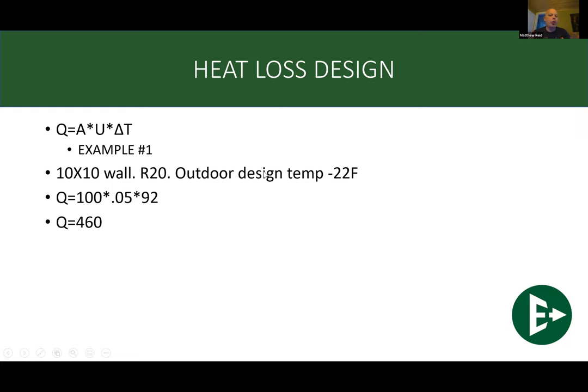So we're going to do a quick little example here. I've taken a standard 10 by 10 wall with R20 insulation in it. I used an outdoor design temperature of minus 22 Fahrenheit. Maybe we're way up there in northern Saskatchewan, something like that. And then we just run it through the formula. So Q equals 100 times 0.05 times 92. 100, of course, being 10 times 10. 0.05 is 1 divided by 20. And then the temperature differential, where we're going from minus 22 to 70, is 92. So the heat loss for that particular wall is 460.